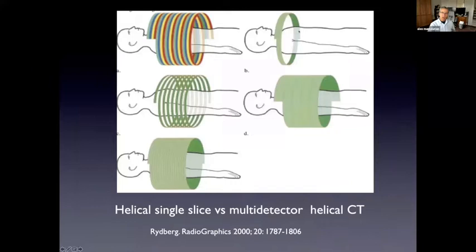So the pathway that this scanner takes in a single slice scanner or single detector scanner done helically is like this. Now we can set the detectors as relatively wide, we get this wide ribbon. Or we have this scan with high pitch, so we have gaps in between the bands. Or we can do what's called multi-detector scanner, where we go through the same path, but now we have multiple detectors and allows for a wider beam, but more data that is acquired closer together.